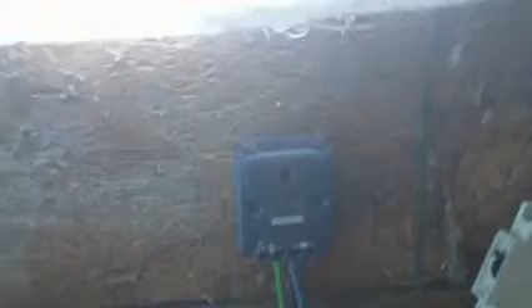So I've done a stunt that a lot of people think is quite dirty. What I've done is tapped my battery bank so that this is only reading the voltage of one 12 volt battery, so it thinks it's connected to a 12 volt system. The way that's done: the positive of all the 24 volt solar panels comes through and combines in the breaker, as I said, and this wire here connects directly over down here to the positive of the batteries. So it doesn't go to the charge controller at all. Bear in mind, one important thing to note, this is a common positive/negative switching charge controller, as a lot of the cheap little Chinese ones are.